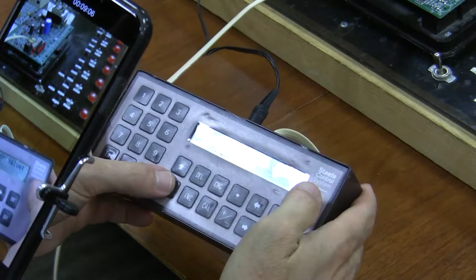But if you come to one of these outputs that say automatic, then I could come to this particular one and say I'm going to change it. I'll scroll it and say I'm going to manual you on. And if I hit enter, that's going to stay in that position now. If it started out as automatic, it'll stay manualed on until that controller sees a power bump.